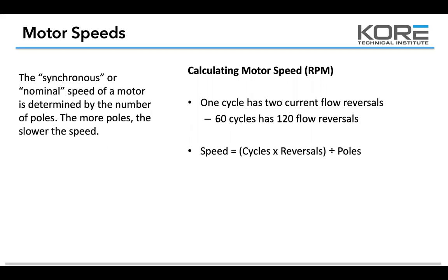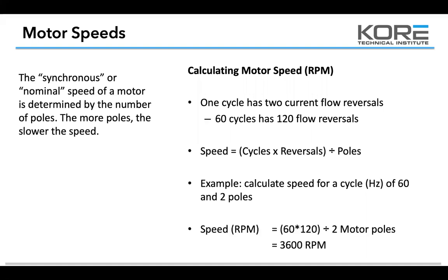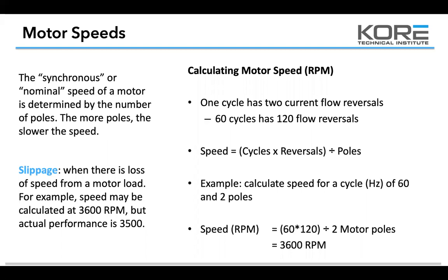So speed is cycles times reversals divided by poles. For example, you calculate the speed of this first cycle, and we're always using 60 hertz. If you have 2 poles in that motor, then you're going to do 60 times 120 divided by the 2 poles, and you're going to get 3,600 RPMs. So this is what I was talking about at the beginning, slippage. Slippage is a loss of speed from the motor load. For example, speed may be calculated at 3,600, but actual performance is 3,500. So you could have a heavy load on that, and so you might get some slippage. It might not be cranking like it would if it's freewheeling.